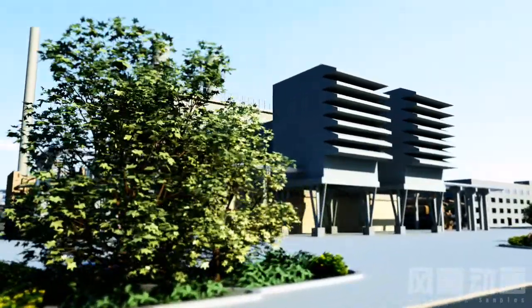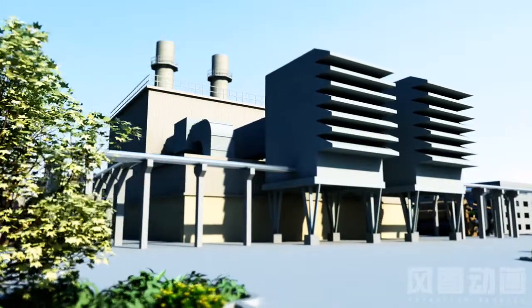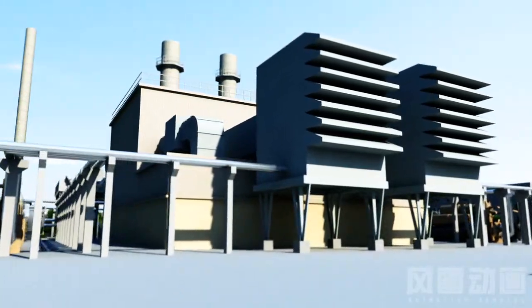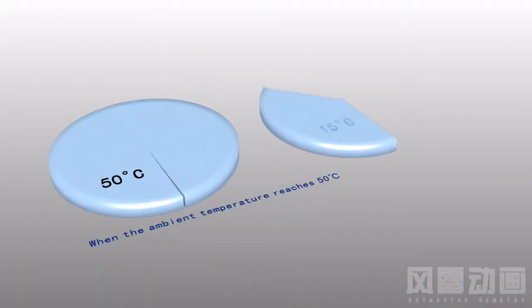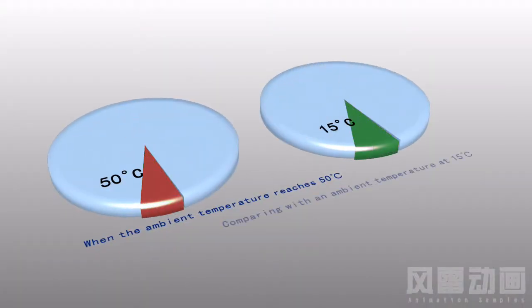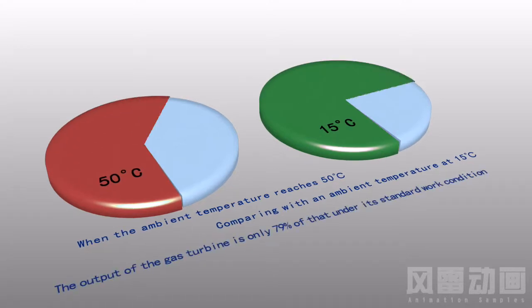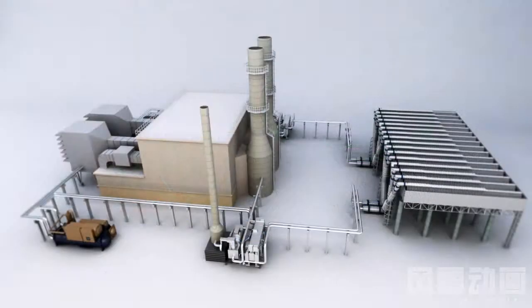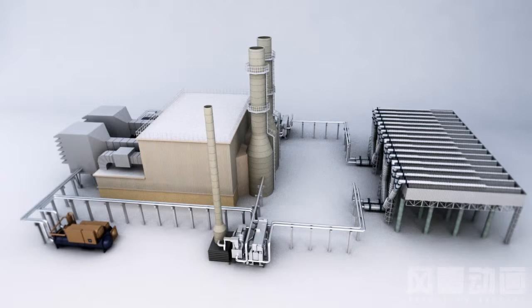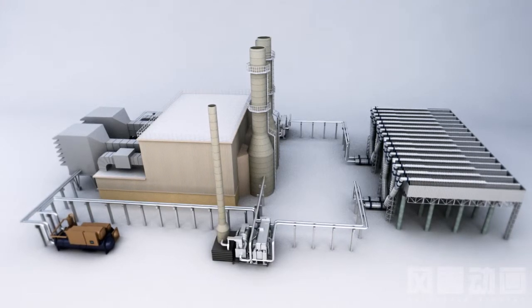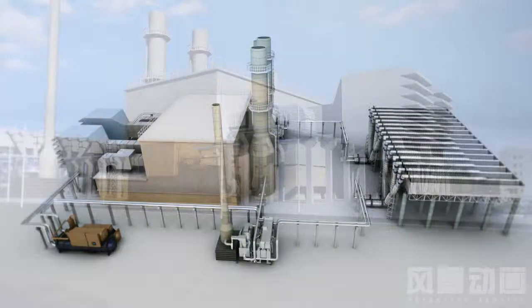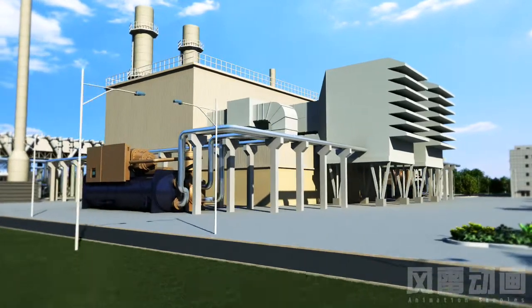But in the Middle East and tropic areas, generally the ambient temperature reaches 50 degrees centigrade. At such an ambient temperature, the output efficiency of the gas turbine is just about 79% of that under its standard work condition at 15 degrees centigrade, resulting in dramatically decreasing of the generation output. Shuangliang flue gas absorption cooling technology completely conquers the drawbacks.